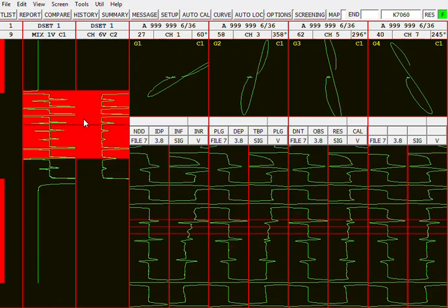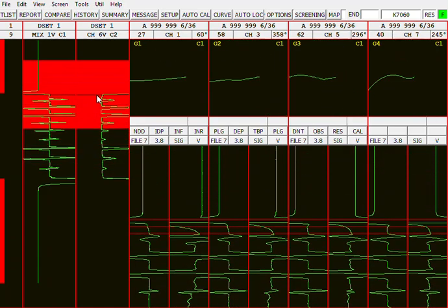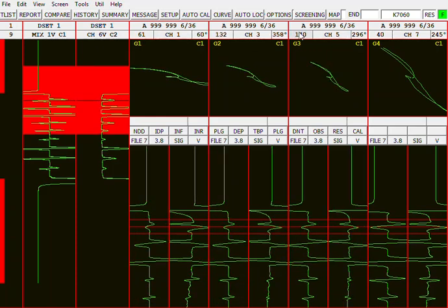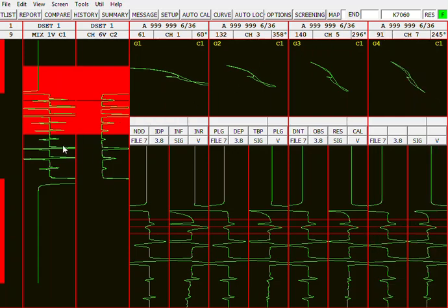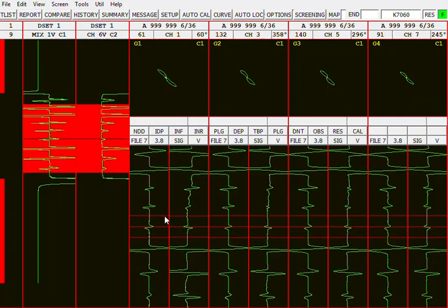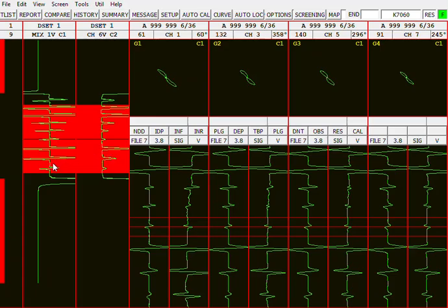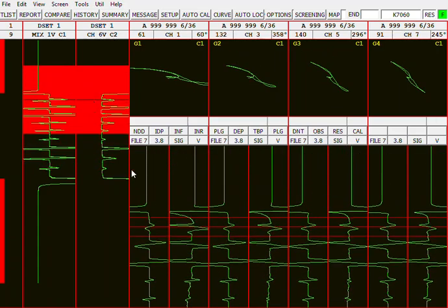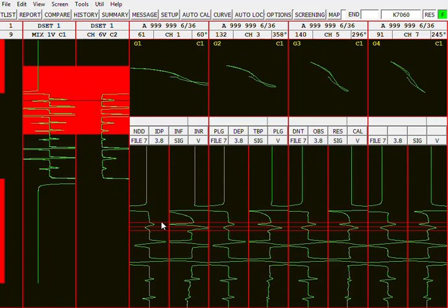Now, if you go to ID flaws, like you have right here, that's a big diameter ID pit. But now remember how we set the 100% hole to 40 degrees here? We know that the OD flaws rotate counterclockwise with decreasing frequency, but ID pits are going to rotate towards the 100% hole with decreasing test frequency.